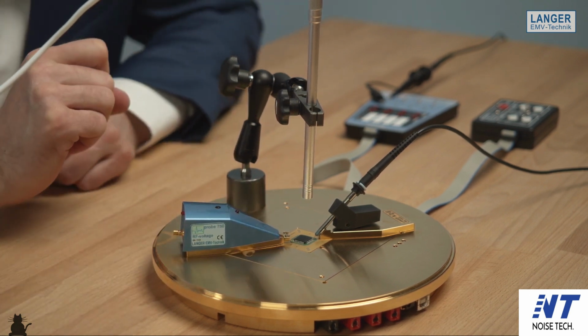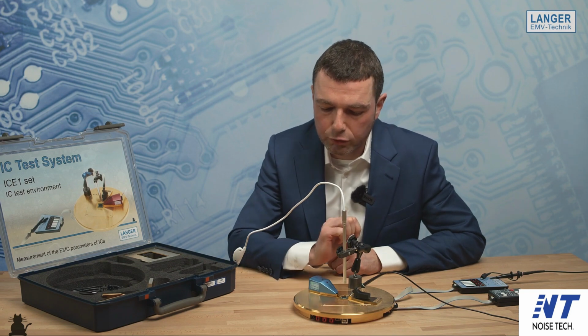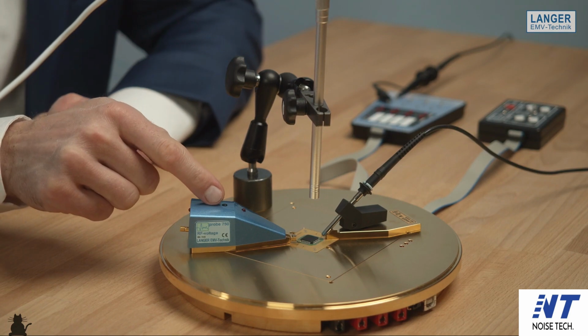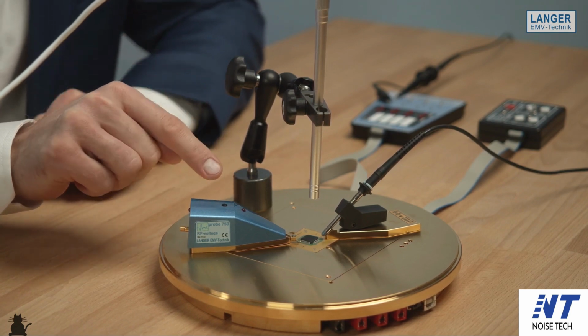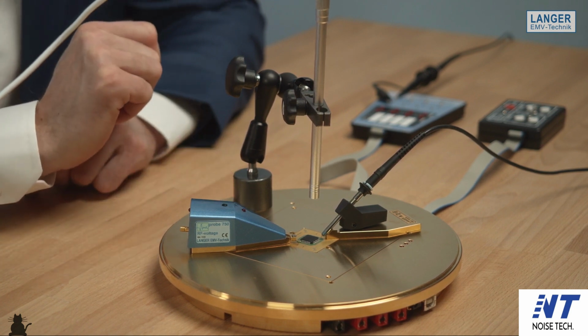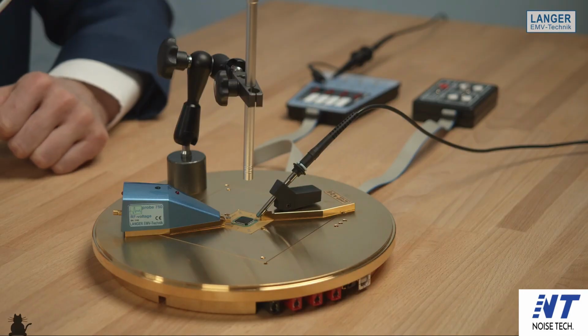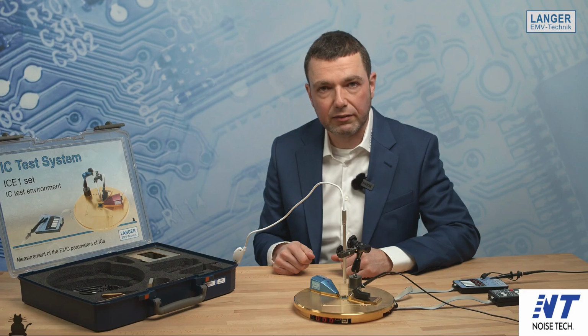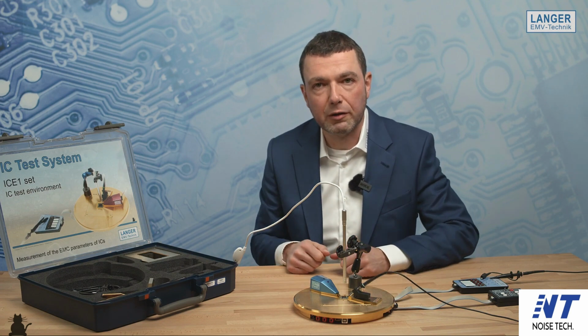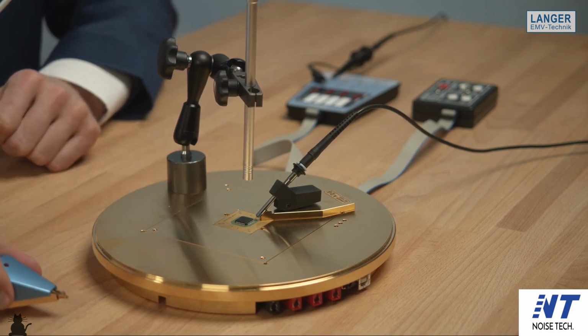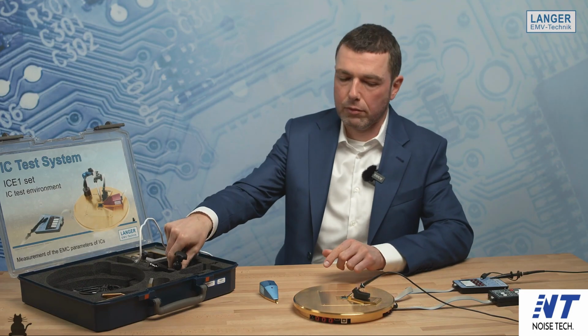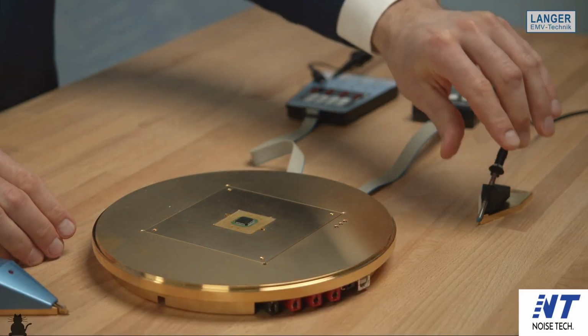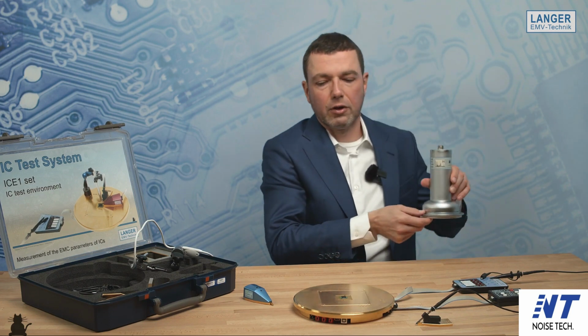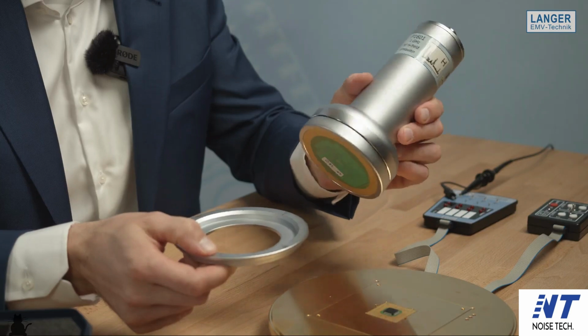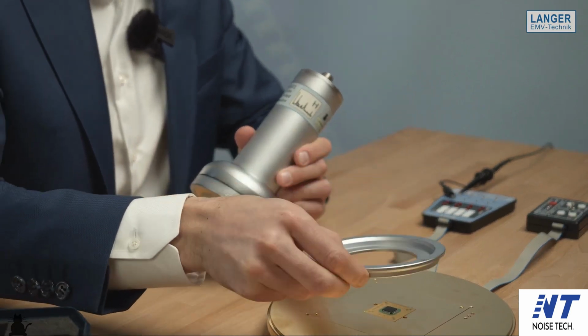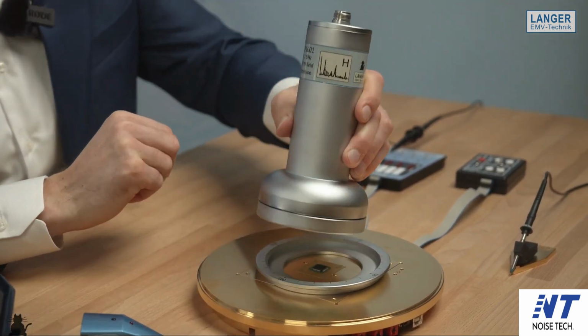With the help of the microscope camera here, you can see if you are connected to the pin or not. You have also an integrated pin detection in the probe, where you can see with the LED here if you are connected or not. This here is a setup for the conducted measurement, and if you would like to do a radiated test, you need some space on the ground plane for the field probe. Now you can take one of such field probes here and you can put this probe with this spacer ring in a defined distance above the IC.